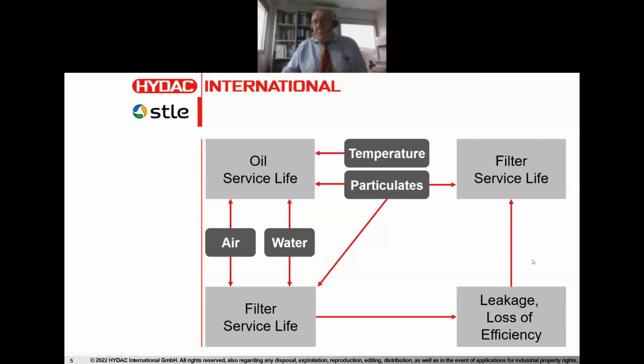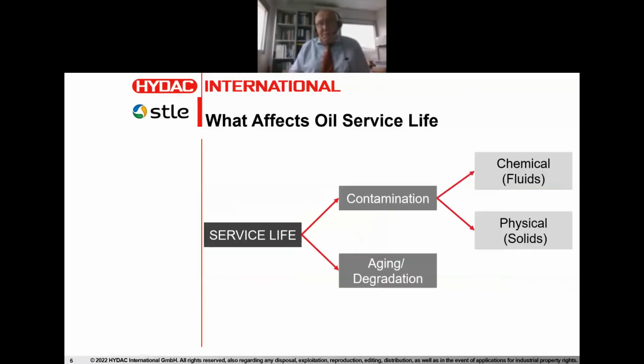Loss of leakage efficiency on the pumps also affects the filter service life, temperature, and particulate. So we can see that there is a complex interplay. And one of the big issues, or maybe drawbacks, with how online condition monitoring has been approached thus far is that it has been in isolation. People do not tend to bring these factors together. So very often I hear that my particle count is elevated, but my filter service life is not decreased. So either the filter is in bypass or the particle counter is reading wrong. But if you take them in isolation, then you can obviously arrive at erroneous conclusions and you get a misleading picture of what is happening within the system.